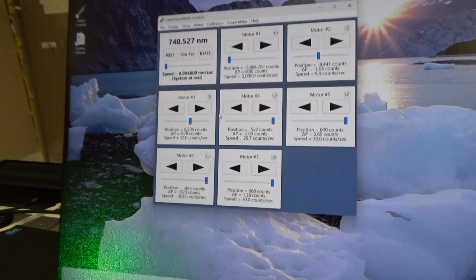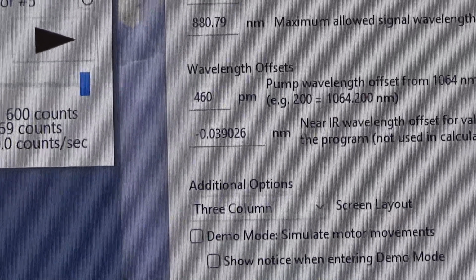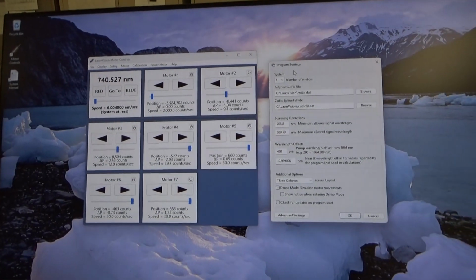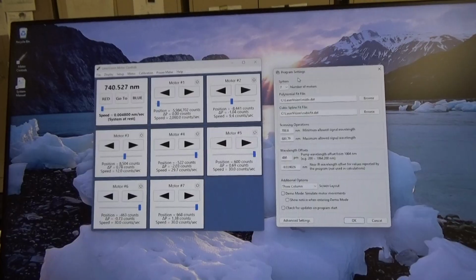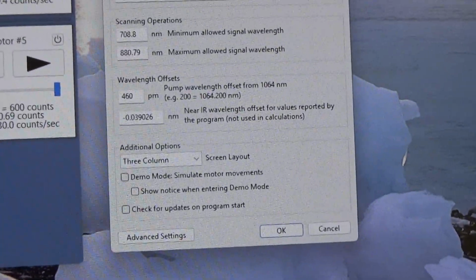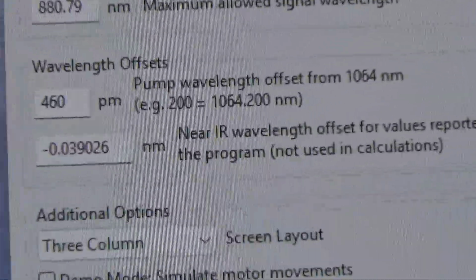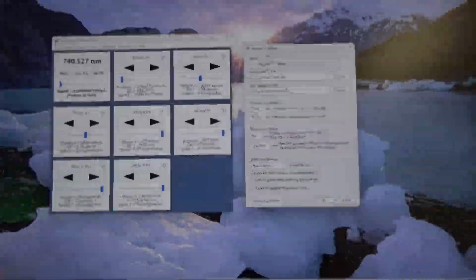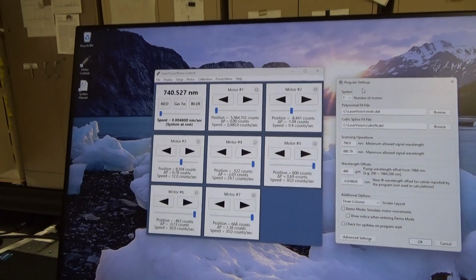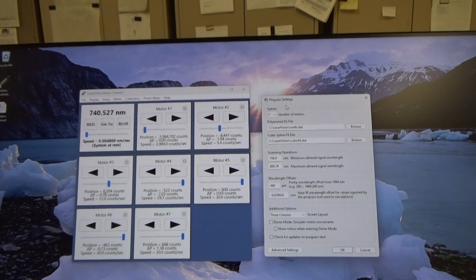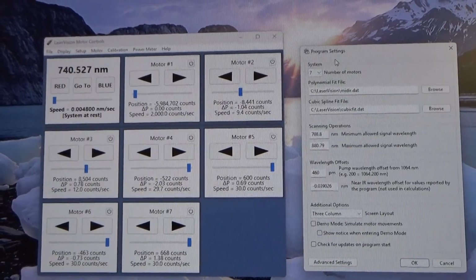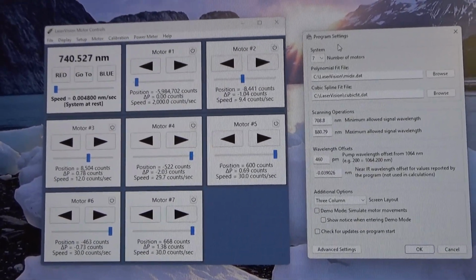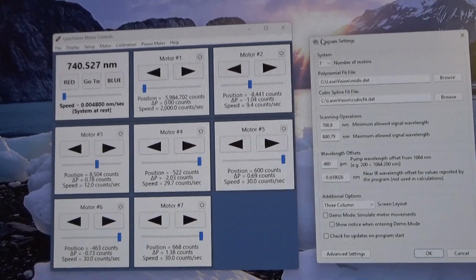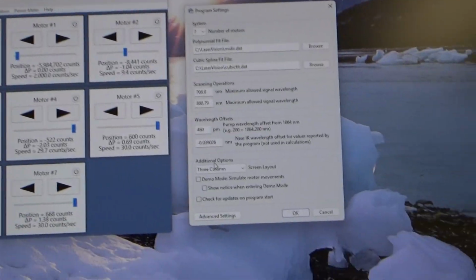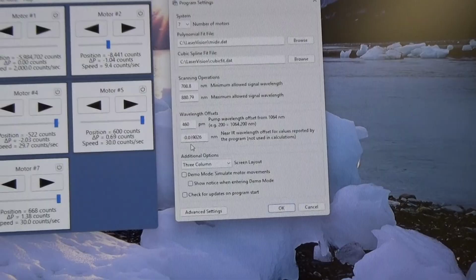Now, that step of going to a known spectral feature, measuring where it is with respect to the displayed wavelength in your system, and deriving an error that you enter into an offset for the near IR wavelength is all that you need to do to recalibrate the system. That's because we're using the velocity mode. Only the wavelength needs to display correctly. The absolute positions of the motors for the crystal motors do not matter. I can change those values to any value at all, and the system is going to tune in exactly the same fashion as it does. So the offset is the only calibration that needs to be done for the system.